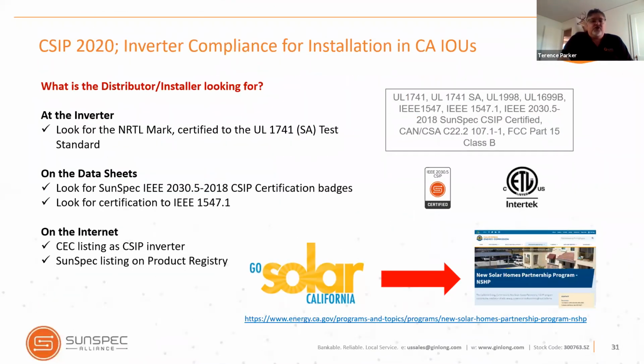They need to look at their inverters and confirm this is a UL 1741 SA tested standard inverter. They can check their data sheets and look for the SunSpec IEEE 2030.5-2018 CSIP certification badges. If you don't see it on the inverter nameplate, you'll definitely see it in the spec sheets.